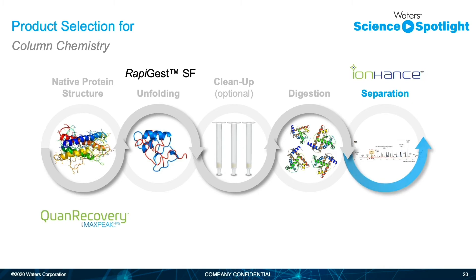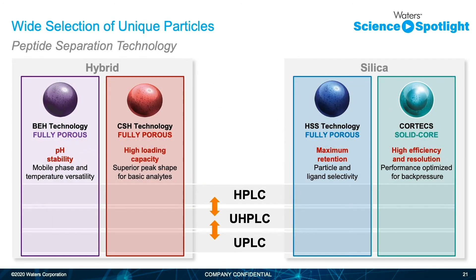Moving on to column chemistries — they are either your most comfortable playground or a completely foreign language, but I promise they are excellent tools to keep in your toolbox. Waters offers a very wide selection of unique particle offerings with both hybrid and silica-based particles, both fully porous and solid core particles, all with various bonded and unbonded options. I often refer to BEH and HSS technologies as the grandfather and grandmother of chromatography. BEH is the original hybrid particle, HSS is a more traditional silica particle, and then CSH and CORTECS are really the new kids on the block. CSH stands for charged surface hybrid, and CORTECS is a silica particle with a solid core providing really excellent efficiency.